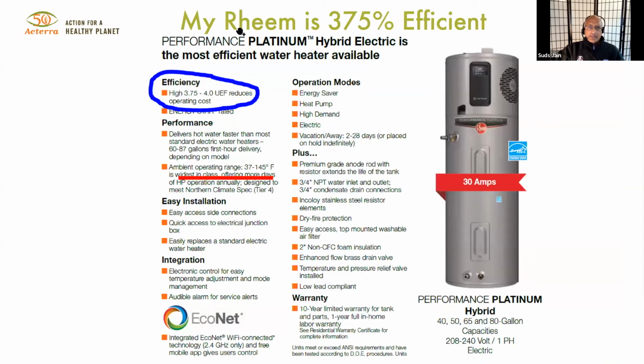Okay, so this is my heat pump water heater. As you can see, it has an efficiency of 375 to 400%, and the ambient temperature it'll work at is 37 to 145 degrees. A lot of people put these in their garages, and the garage air comes in. If it's colder than 37 degrees, there's an electric resistance element in here that'll just heat the water like an old electric water heater.